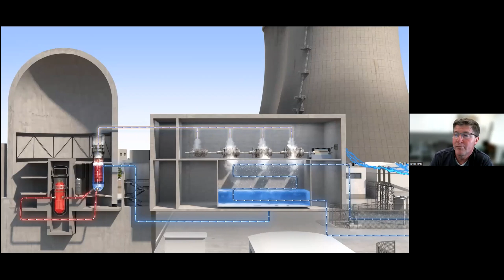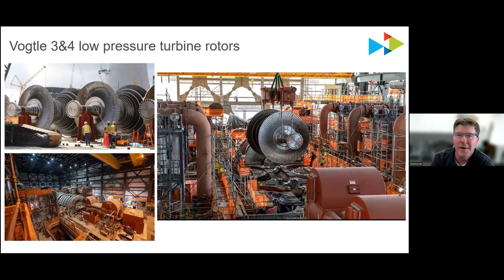Now, for size purposes, these are the new turbine rotors. I think it's a mix of unit 3 and 4 photos here. These are the 3 low pressure turbine rotors. Of course, they're all attached, end to end on a shaft. And then we've actually conducted what they call hot functional testing. We have spun these turbine rotor generators at unit 3, 1800 RPM for like 15 minutes. All right. And then unit 4 yesterday, maybe over the weekend, we put it on our turning gear and ran it for a period of time. So we have run and spun our turbine generators a little bit, but not yet to make electricity.